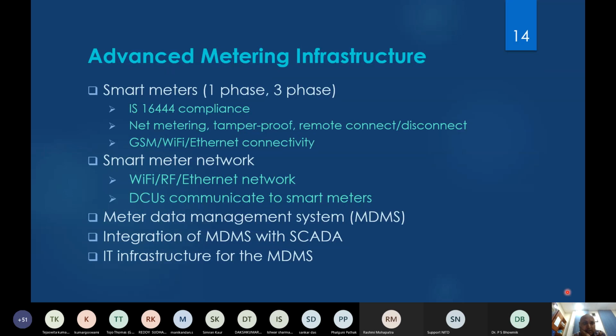When we started installing the system, we followed IS 16444, the Indian standard for smart meters, but unfortunately none of the smart meter vendors could give us certified meters. All they could provide was a declaration that their meters conform to the standard. We tested those inside the campus, but at that time there were only two testing agencies in India, CPRI and ERDA, and there was a long queue, so it took a long time. Now, though, we do have tested, certified meters.